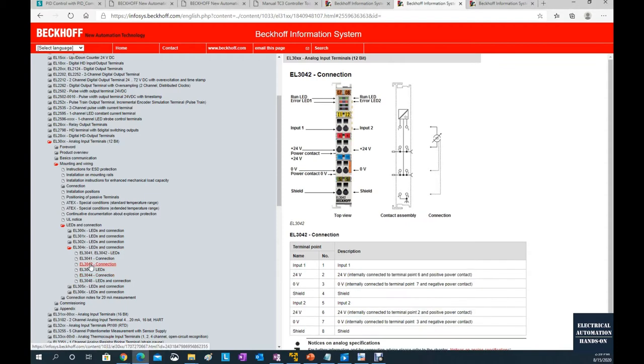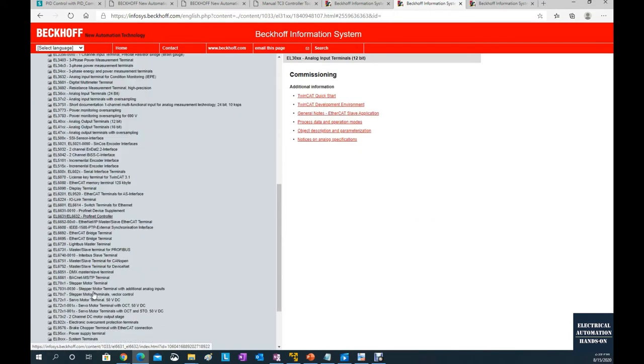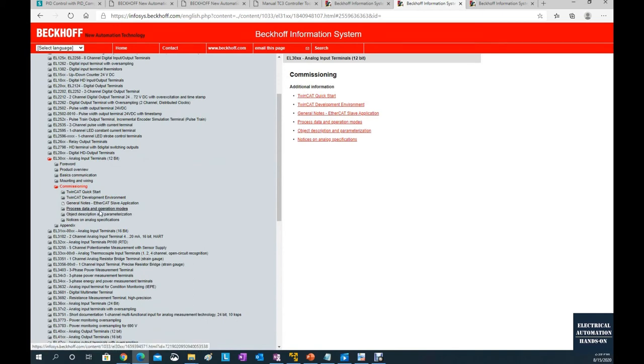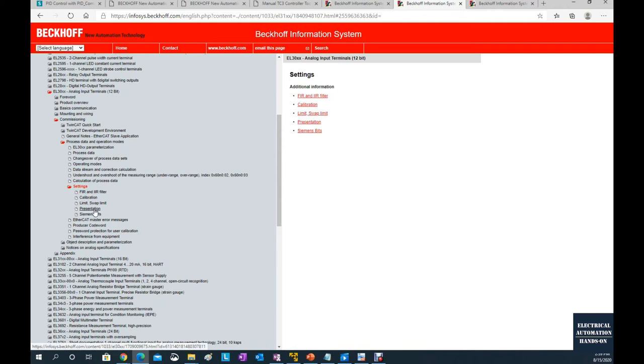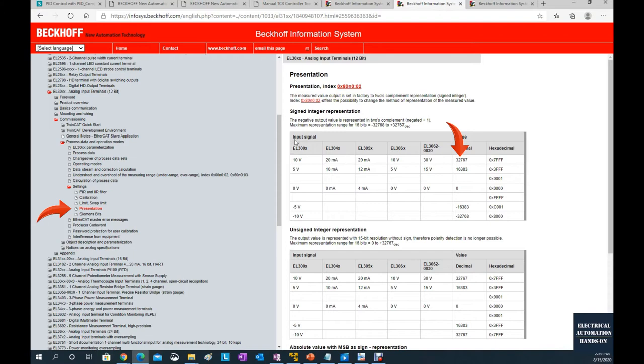If we go to EL3042, we see a similar wiring diagram. For the EL3044 analog card, we need to find the full range. Going to the commissioning section, then process data and operation modes, then settings, then presentation — we can see the input signal table. For the analog voltage card at 10V, the full range is 32767. For the current card such as the EL3044 with a range of 0-20mA, the decimal full range is also 32767. This value is very important — we will use it to scale our analog input.